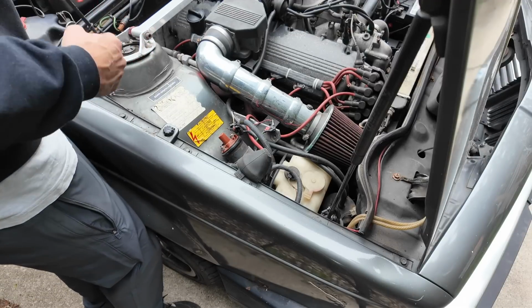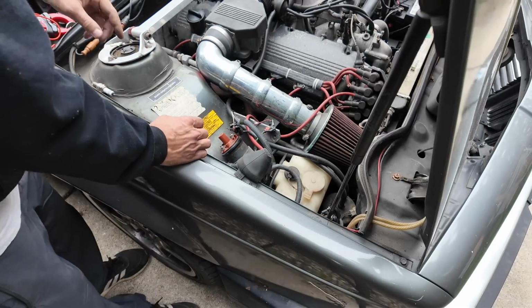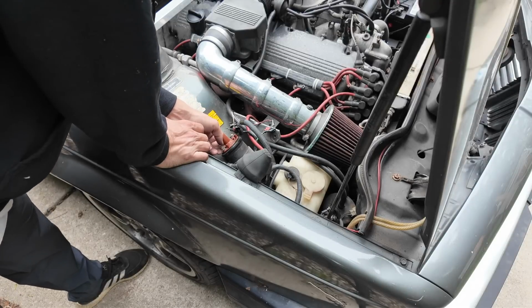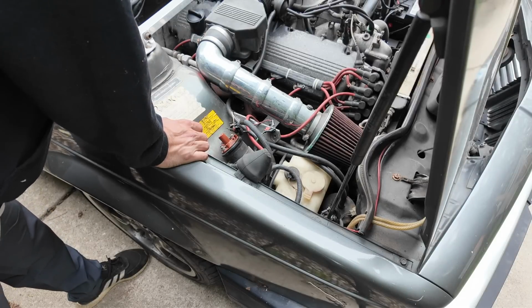As you can see here, 5.8 kilo ohms, so we're at about 5,800 ohms. That tells us the coil itself is all good. The resistance, I hate checking resistance. Multimeters usually suck and don't actually do a good job of it. But that tells us our coil is seemingly all good.